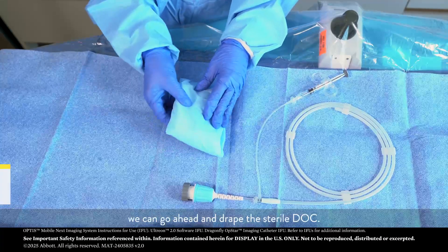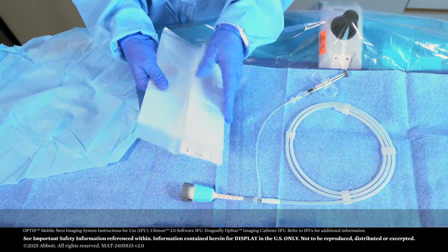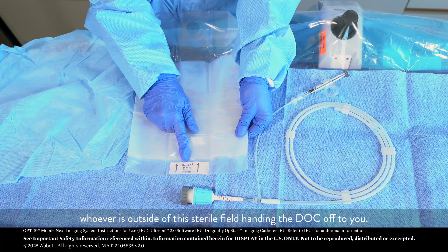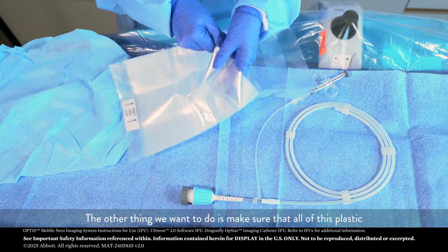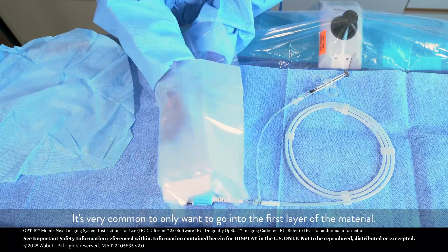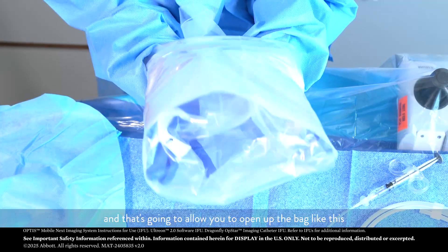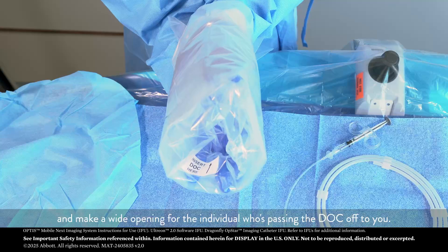So once your catheter is prepped, we can go ahead and drape the sterile DOC. You'll unfold your DOC from the wrapping, and this open portion of the bag is going to face you, and the portion where it says 'insert DOC here' is going to face whoever is outside of the sterile field, handing the DOC off to you. Make sure that all of the plastic is on either side of the top of your hands. You want to have all of that material on either side of your hands, and that's going to allow you to open up the bag and make a wide opening for the individual who's passing the DOC off to you.